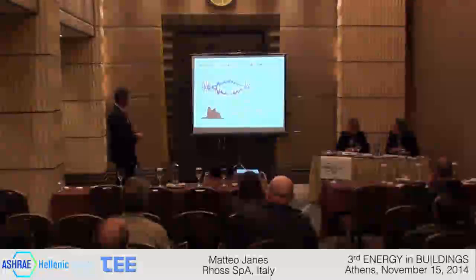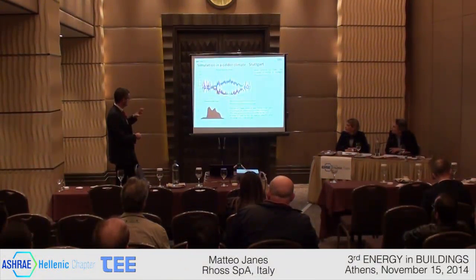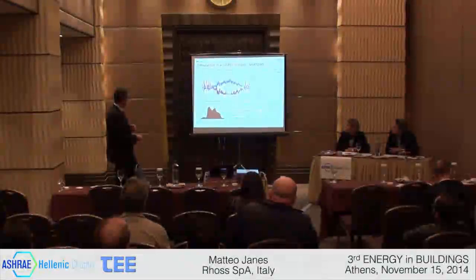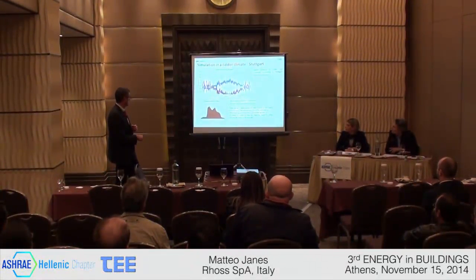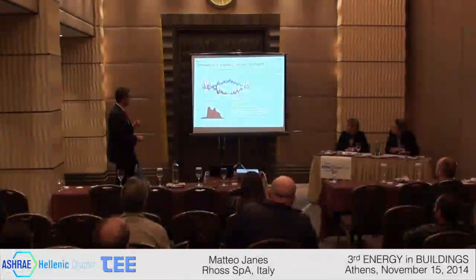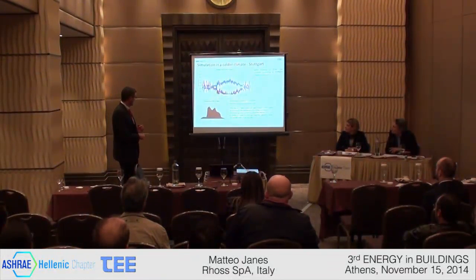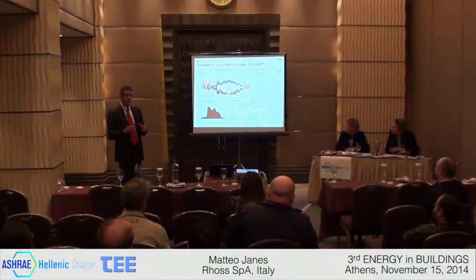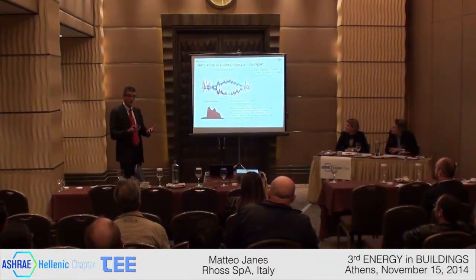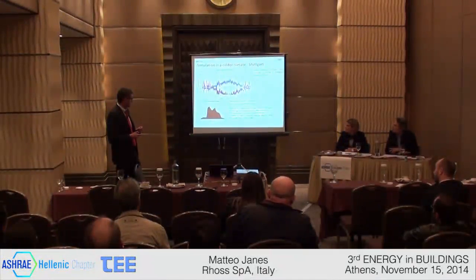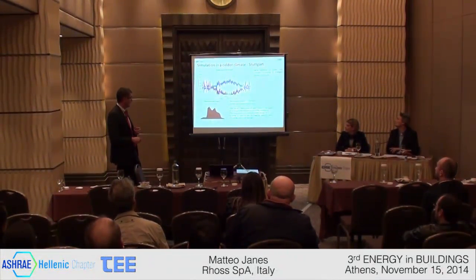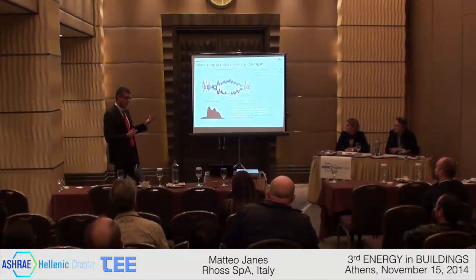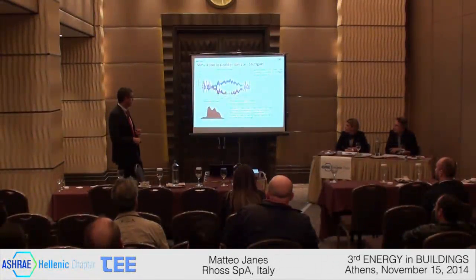This is the energy modeling of this building in the climate of Stuttgart, and this is the temperature profile of Stuttgart, which ranges from -13 to +29 all year round. This situation makes the use of a heat pump all year round not economically convenient, because the operation of the pump with this very low temperature is not energy efficient. For this reason, it was decided to simulate a hybrid system made by a polyvalent heat pump and a boiler, where the boiler is used below -5.